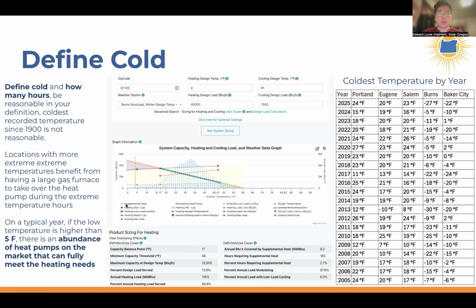You can see here that you have a lot of the blue bars in the area where the heating demand is exceeding the output that the heat pump is capable of.